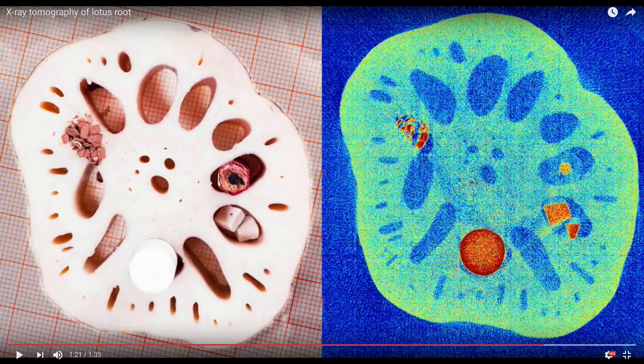Here I made this fancy looking quick and dirty reconstruction using the ifanbeam command in MATLAB. What you will get from the measurement is the sinogram. You can get all the full images if you want, but what you really use in the tomography is just the sinogram containing one row from each image. You will get this kind of quick and dirty reconstruction with ifanbeam so that you can see that something reasonable is going on in your data.